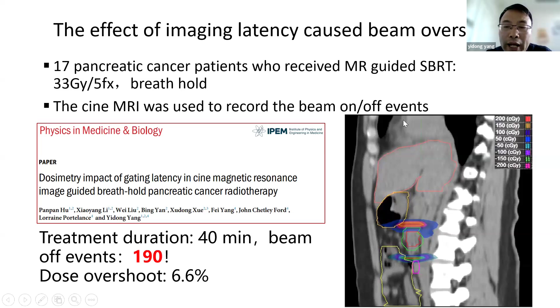And beam on events, this is very important, is more than 100 times. So that means this one time 0.25 second is a pretty large time. So we cannot ignore it. Finally, the dose overshoot is about 7%. So that means we have to pay attention to this gating latency. So after this study, we suggest we should use maybe active control when we use this image-based gating technique.